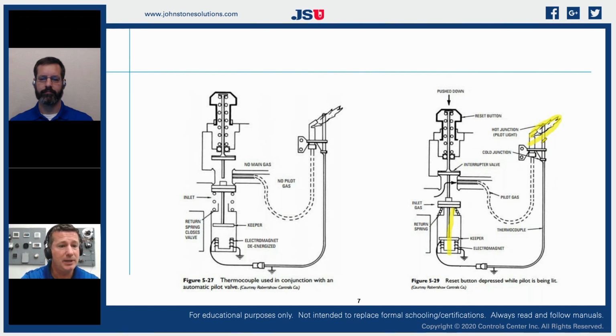So that if there was some interruption, if I have a backdraft of flue and it is enough air that it blows out my flame, I'm going to stop producing voltage on my thermocouple or my thermopile, however you prefer to call it, and it is going to release the solenoid on my plunger and allow my plunger to close and shut off the gas supply, and that is my safety control on a gas valve. And that's what we used forever. So we got used to using that principle.